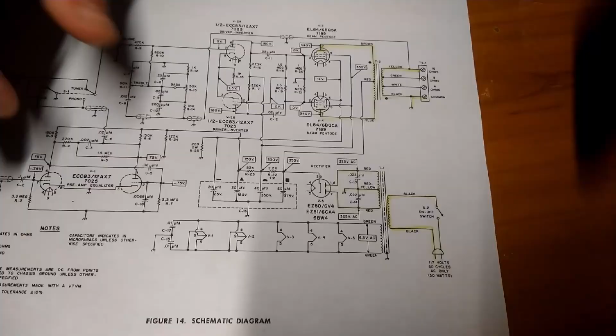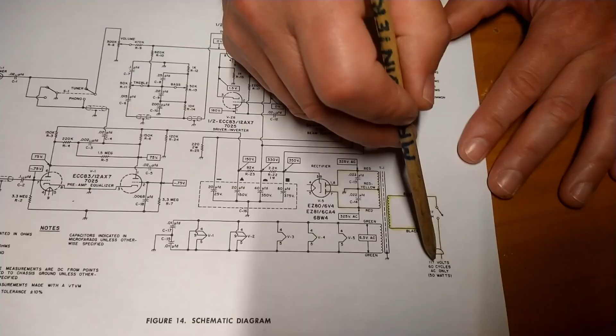Let's move you over here a little bit, put you in the middle. Okay, here is our plug. What we want to do is make sure we can read DC resistance from one prong of the plug all the way through the winding of the transformer, the primary, and all the way back to the other prong. Notice here we have this little arrow symbol - that's the symbol for a switch, the on-off switch. So when we connect our probes, we've got to make sure that switch is in the on position, or we will definitely not have continuity.